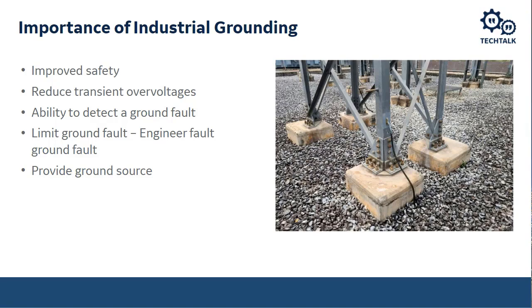Basically, in that case, we're going to be engineering the ground fault. We're going to be engineering the level of ground fault that we introduce into the system. Finally, it provides a ground source for other system protections, other zones supplied out of, for example, if we're talking about a generator or transformer, the zones that are outside of those zones of protection.